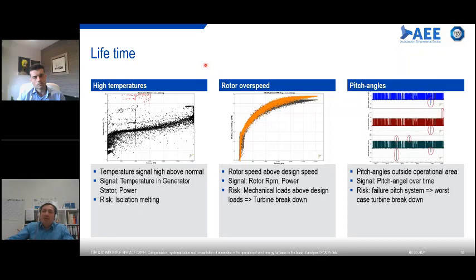Here we have other examples of how to identify problems. In this case, I have a plot of the power output of a turbine versus the temperature in the stator. As you can see, there is a very clearly visible curve in which, for a certain power output, the generator should produce a certain temperature. What we can see here are a lot of operation points way above this temperature level. One risk, of course, as happened in the stator, is that the insulation can melt and we get a short circuit. Again, we have a lifetime reduction.